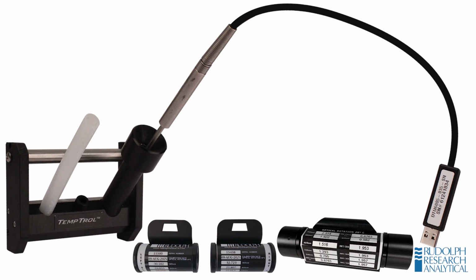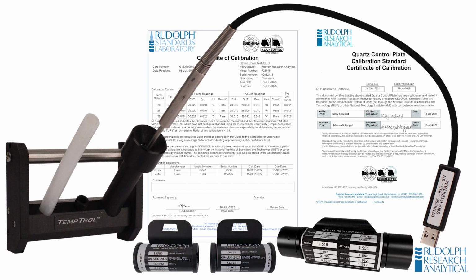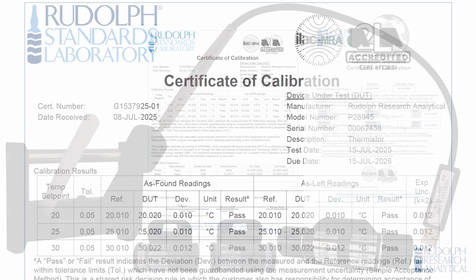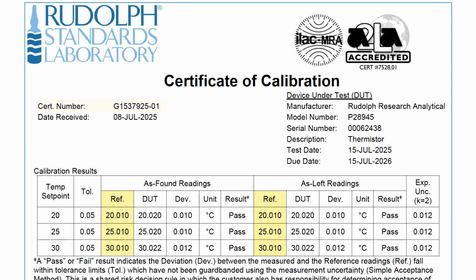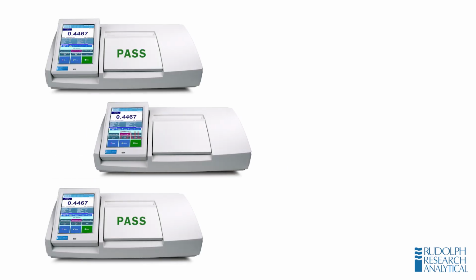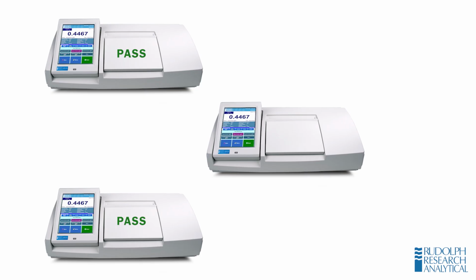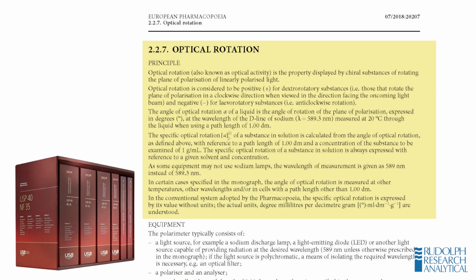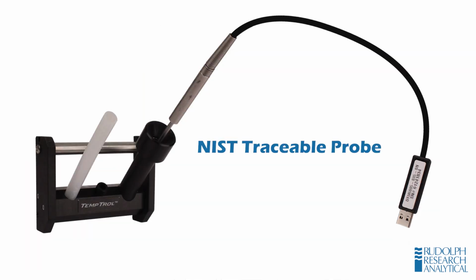Next, calibration and traceability are at the core of every compliance system. Instruments must be calibrated using standards traceable to NIST. Calibration records have to show the standards used, certificate numbers, results, and pass-fail status. If a calibration ever fails, the instrument must be quarantined and requalified before being returned to service. Temperature control is equally important. The pharmacopoeias require optical rotation measurements to be performed at a tightly controlled temperature, since even small fluctuations can alter results. Verification of temperature accuracy using NIST traceable probes must be done during qualification and checked regularly.